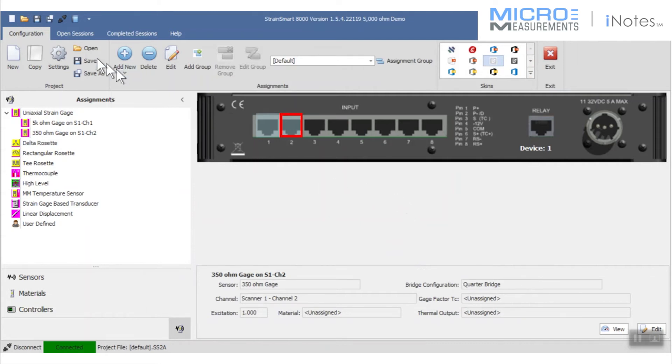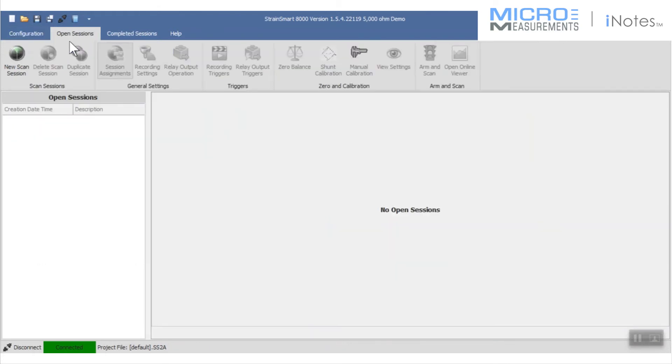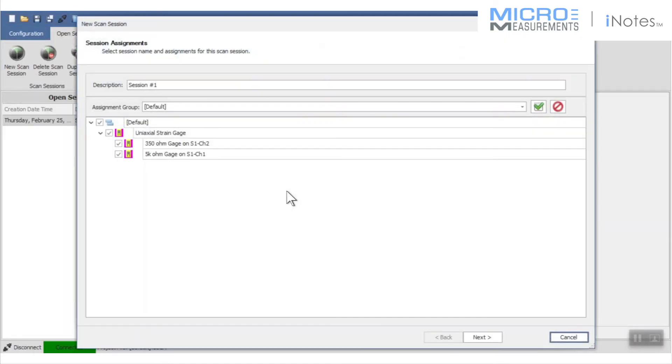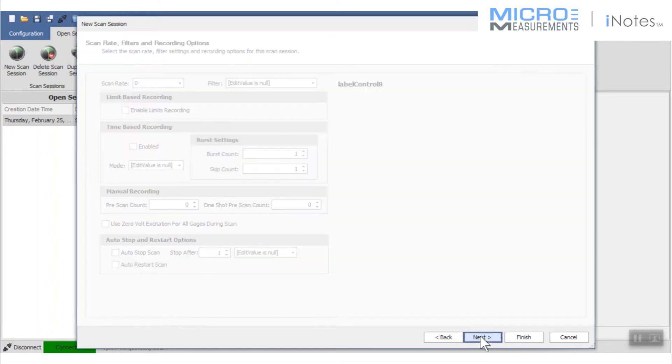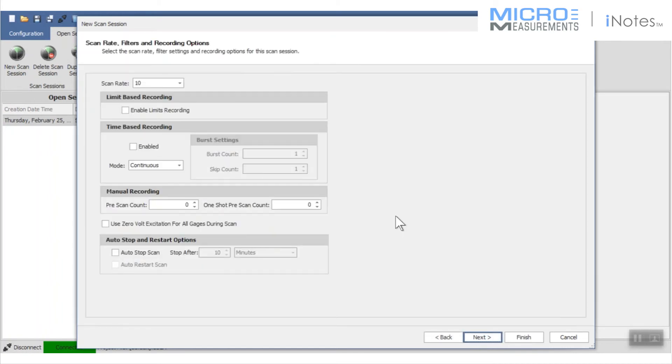Now that I've got two strain gauges connected, I'm going to create a scan session. Again, not trying to get too deeply into what the StrainSmart software will do, but with the scan session, it'll default to the sensors that I've included so far. Then it asks me about how fast I want to scan.